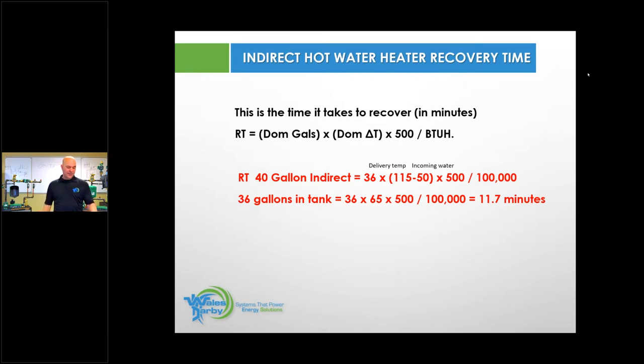All right, so do the math. You have your 36-gallon tank, do the math in your parentheses, then multiply 36 times your number times 500, divide that by your Honeywell zone valve, 35,000 BTU, and send Jim some answers of how long that should take to heat up that tank. Please.